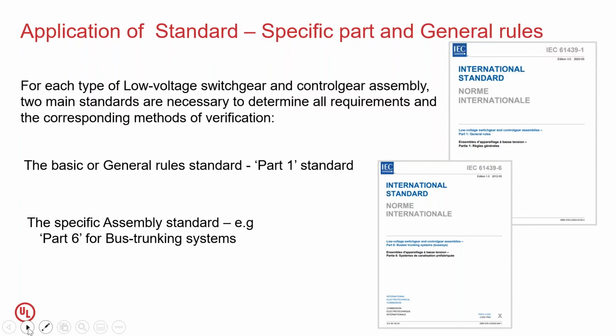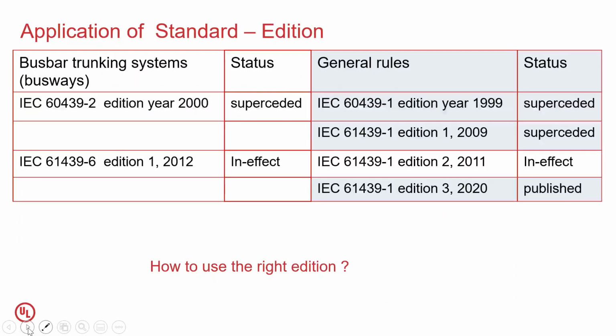Now in the next situation, once you know that you need both the general rules and the specific part standards, also very important is which edition you need to choose. This is a very important understanding needed, especially for regulators and consultants. Now 61439-6 is currently in edition 1, published in 2012. This actually came into effect earlier. There was a standard called IEC 60439-2, and that has been superseded by the 61439-6 series. Similarly, for the general rule standard, there have been 3 editions. The first edition of 61439 came in 2009. Subsequently, we had 2011, and then we now have edition 3, 2020.